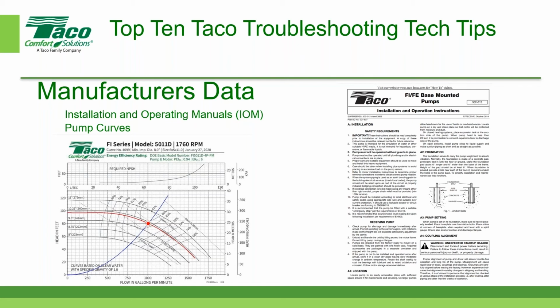Well, the most important one is the pump curve, but in this particular case, we're also interested in the installation operating manual. So I have examples of both here on the screen. The one on the right is the installation and operation instructions, sometimes just referred to as IOMs, and then the pump curve. And if it's a Taco product, I may also do some research on my own to see if there's other data that may be valuable to me. But these are just examples of the kind of data that you need to collect.